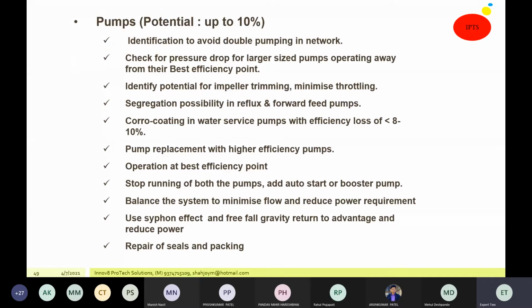Use the siphon effect. At several locations I have seen in my place that gravity flow can also suffice because of the margin given in the design, and we have stopped the pump at several locations. And repair of the seal and packing, because these are all energy consumers, energy losses.